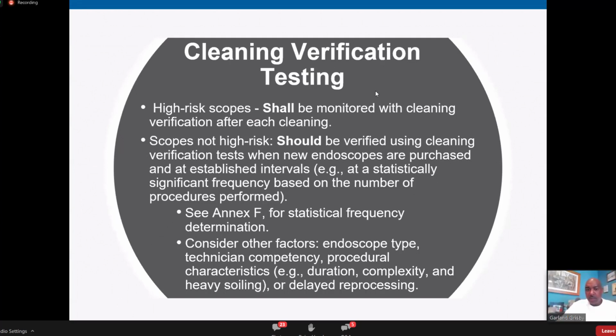So a cleaning verification test or a cleaning monitor is a type of test that's done after the manual cleaning process, but prior to your putting it into an automated endoscope reprocessing machine, an AER, or prior to sterilization. So it's always meant to be done at this point in the process after manual cleaning, because you're verifying that your soil is either not detectable or has been lowered to a level that can't be detected at that test.